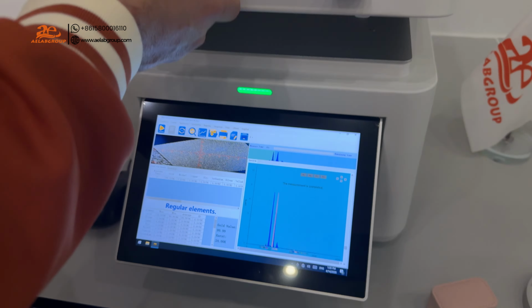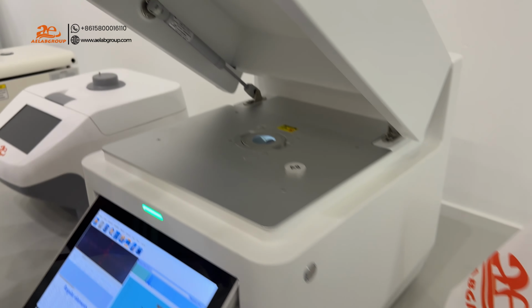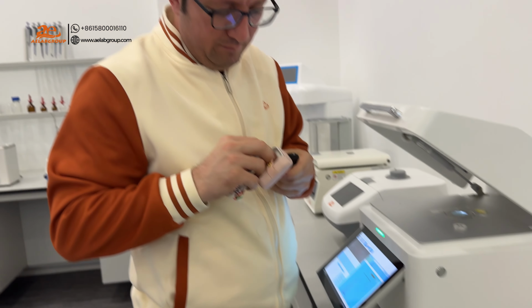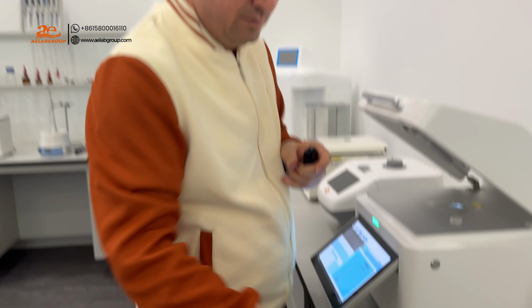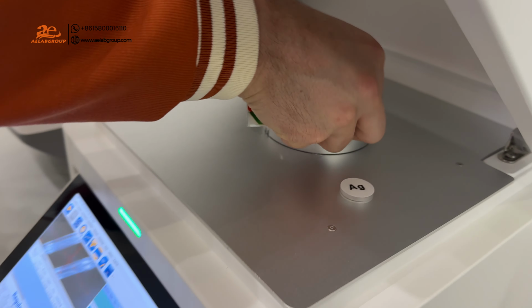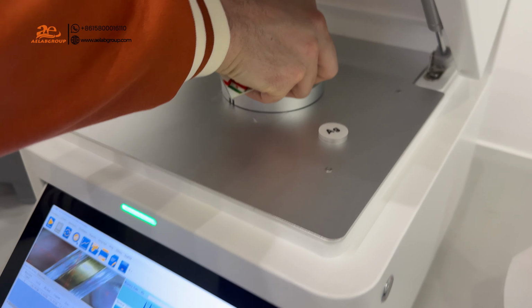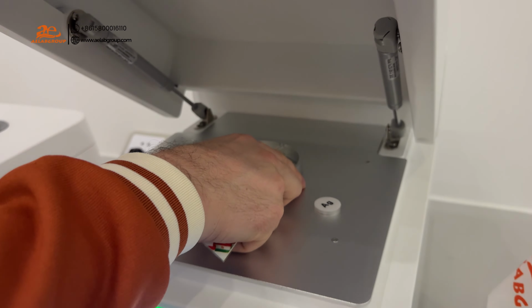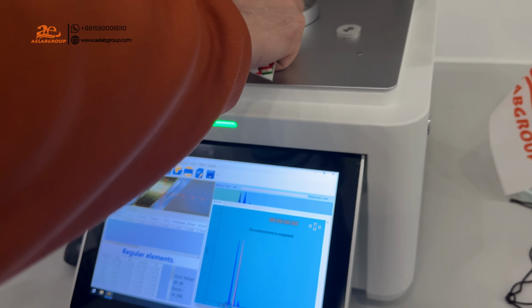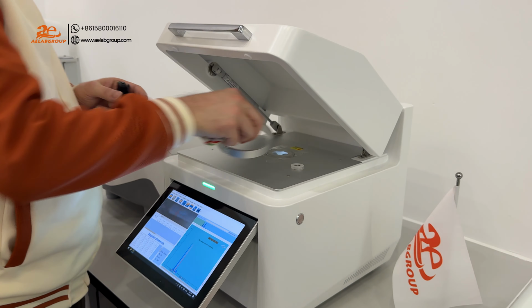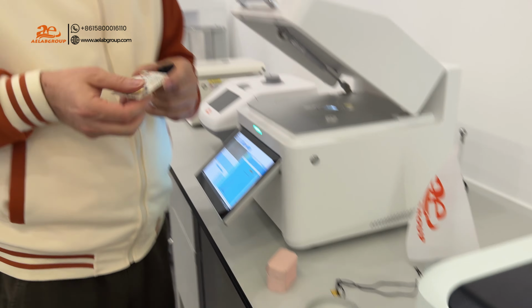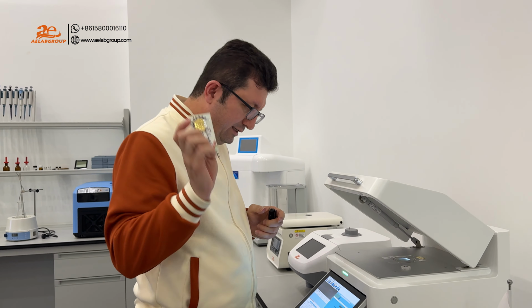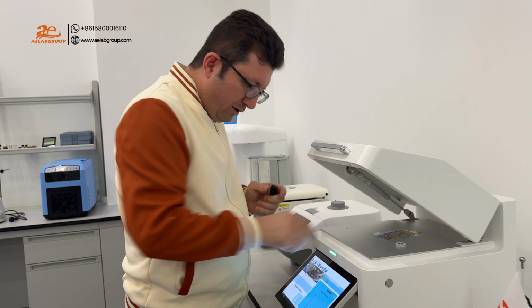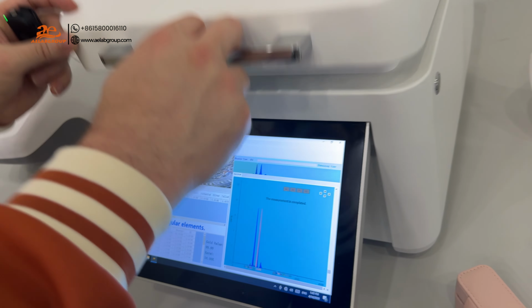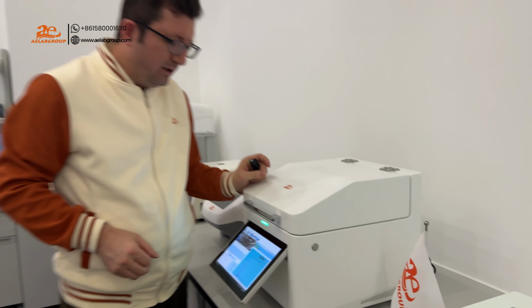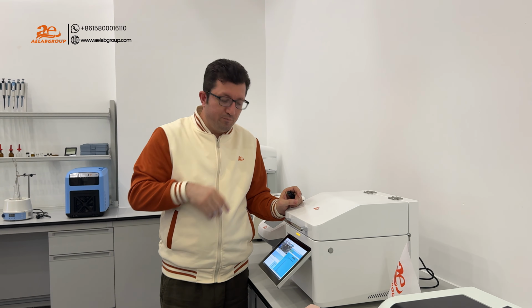So we can also check other golds. For example, if you have some gold like this, it's also easy. You can use this one and put your gold in here. And you can even see the monitor, something like this. You can test your gold. Or if you have silver, it's the same. So we are testing now this type of gold. It's very easy. We just put it here, and in the camera we just fix on one area. After we close, again we push this key, and we wait for 60 seconds.